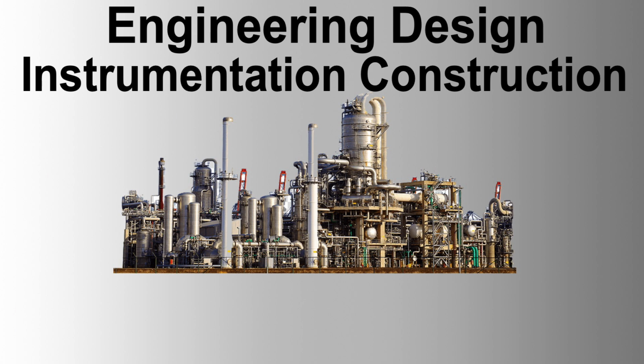Lead-throughs shall be made watertight by means of a sealing compound or by the use of bush couplings. Where welding on instrument process lines is required or specified, it shall only be performed by welders qualified to ASME IX and inspected by approved NDE specialists to the same standard as the associated process pipes, including X-ray requirements.